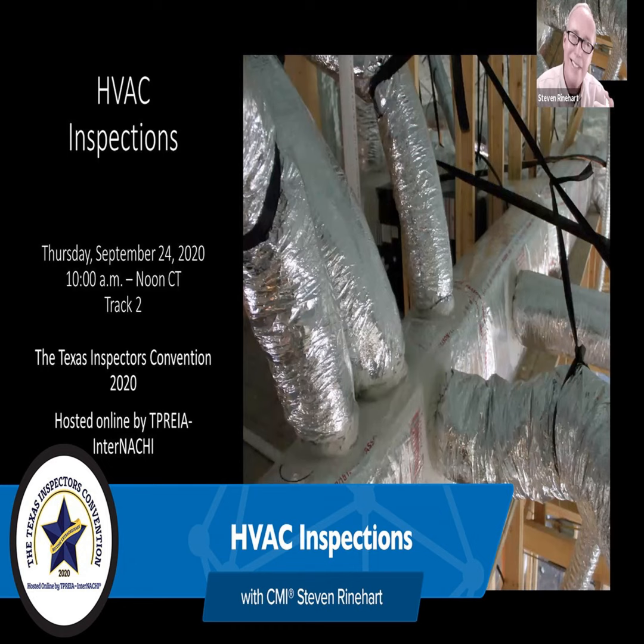Most of the new thermostats now, when you do a setup, it's in the programming. In the setup, you can tell it whether this is a gas or electric furnace, or a heat pump. But if it's not compatible with the equipment, that's a deficiency in the thermostat. I've seen it where I know this is a heat pump, these are heat pump model numbers, and I have a non-heat pump thermostat.